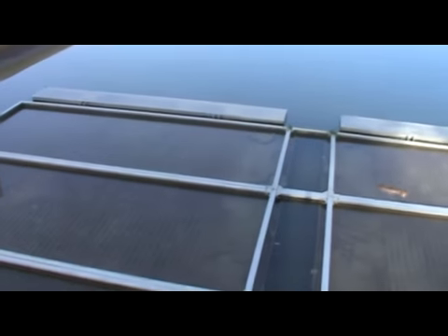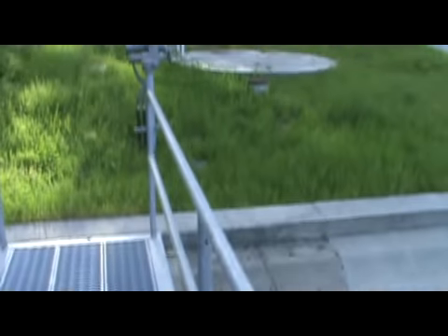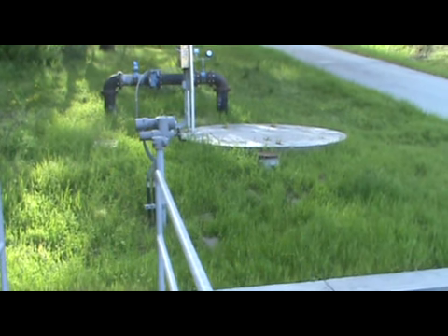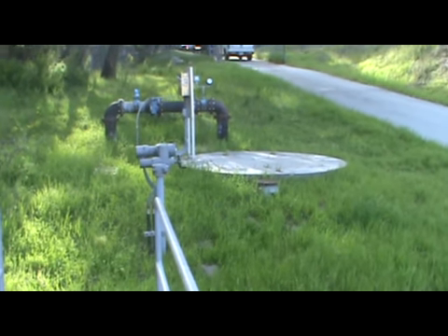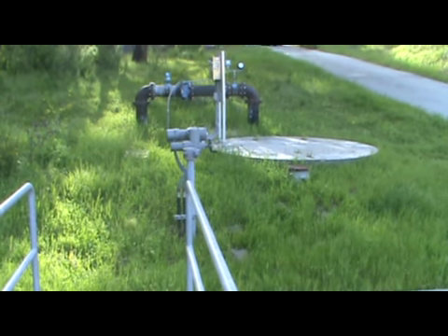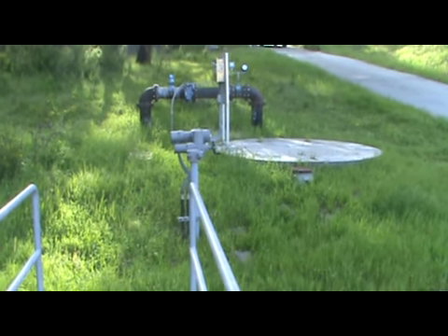And then from here, the water gets recycled. These are some plate settlers right here, and there's a whole series of these, and the water drains through these, and it allows the particles or anything that might be in the water to settle out on these plates, and the water collects through a trough and goes into a sump over here. And then from there, that opens up and drains that water back to the inlet at that treatment plant, and they blend that with the treated water as they bring it into the inlet of the plant, so nothing really gets wasted there.